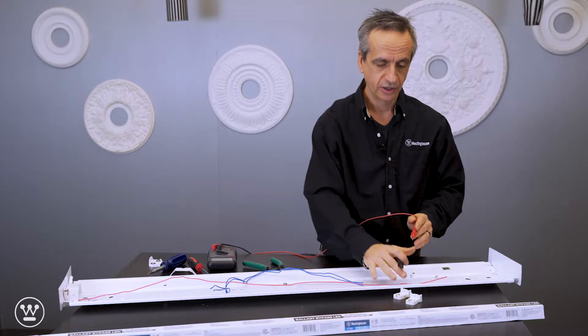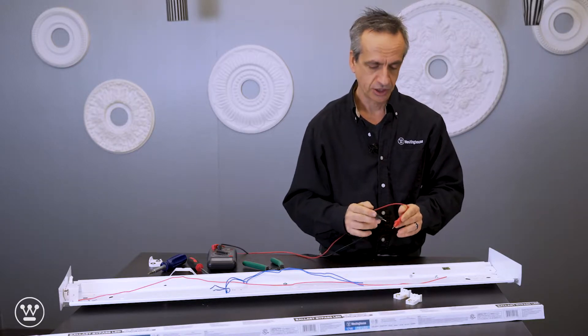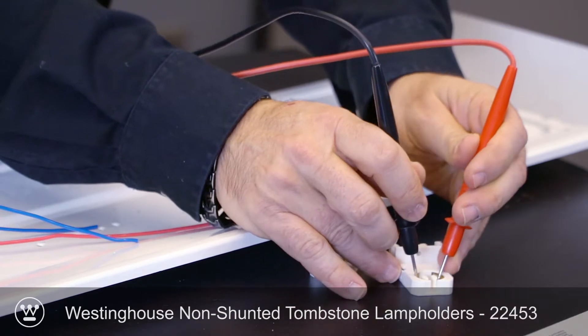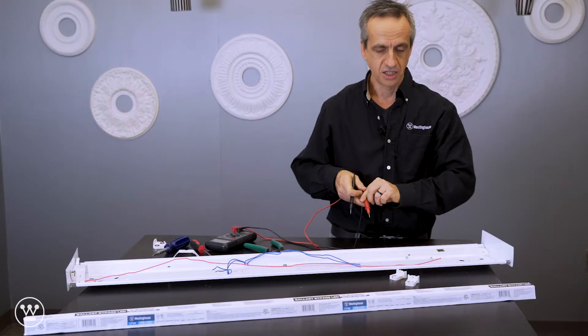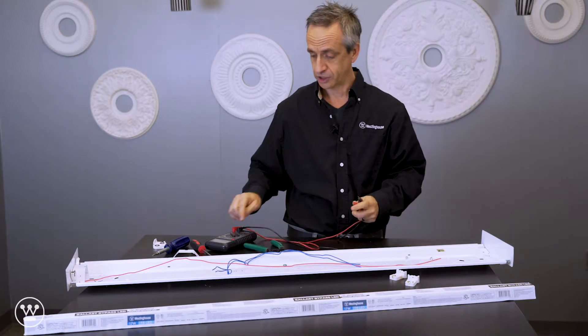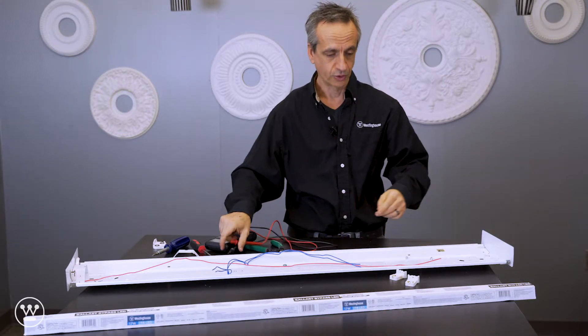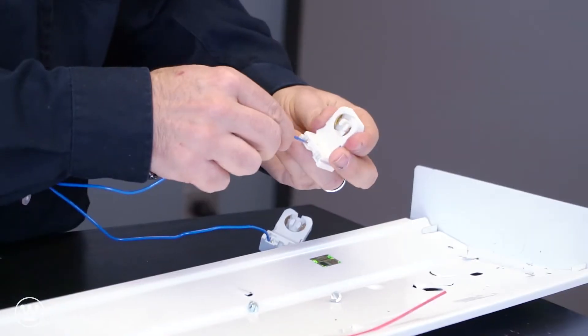We want to make sure that the replacement sockets are non-shunted. We're checking for continuity. And these tombstones appear to be non-shunted. So we'll proceed with wiring up these tombstones.